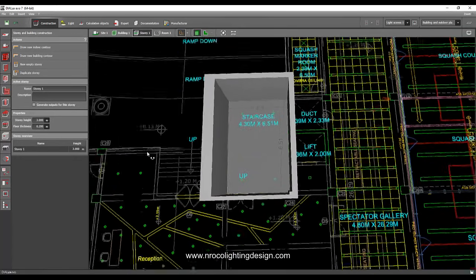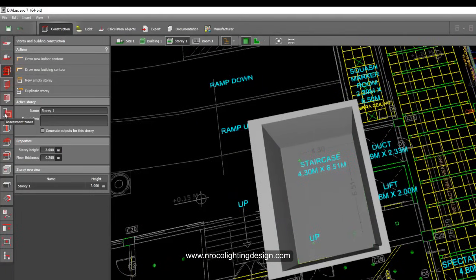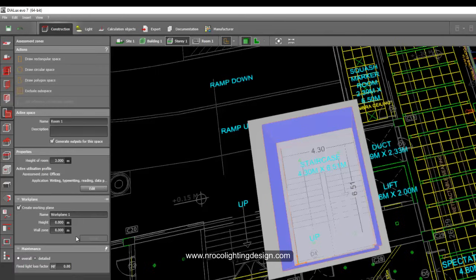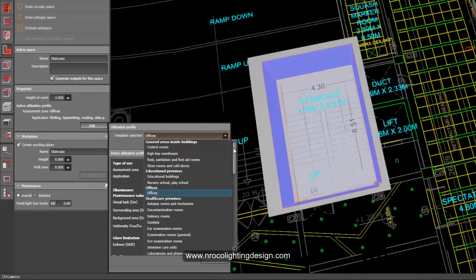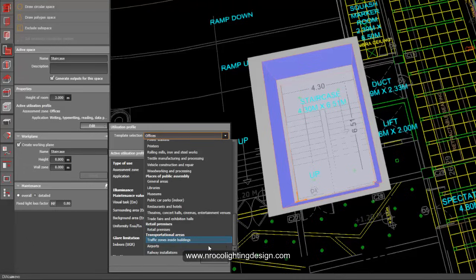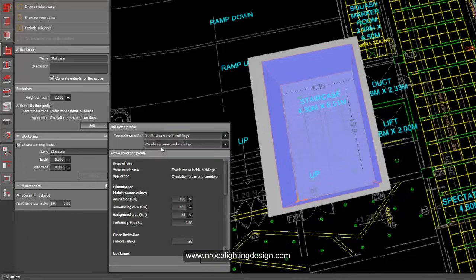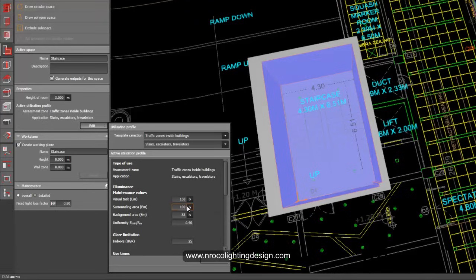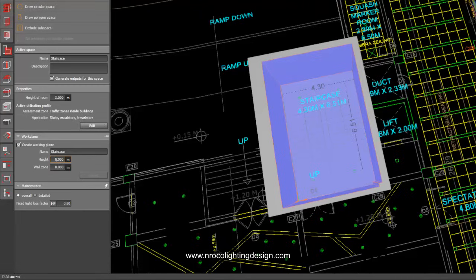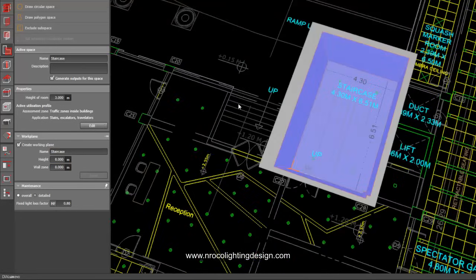Once we've created the room for the staircase, go to the assessment zone, click it and label it as the staircase. Then go to Edit — the default in DIALux Evo is offices — so select 'Traffic zones inside buildings,' then select 'Stairs.' Now it shows 150 lux as the requirement. DIALux Evo follows the same standard: 150 lux, uniformity 0.4.